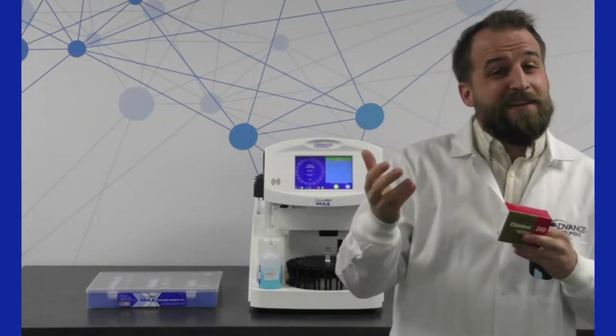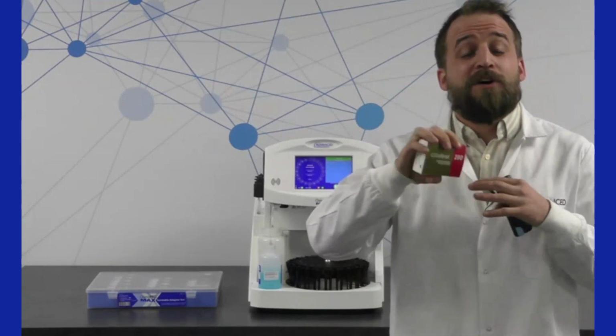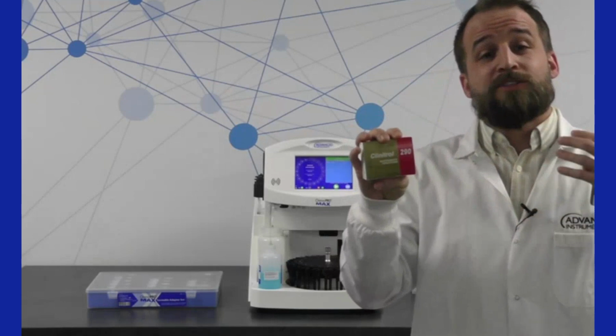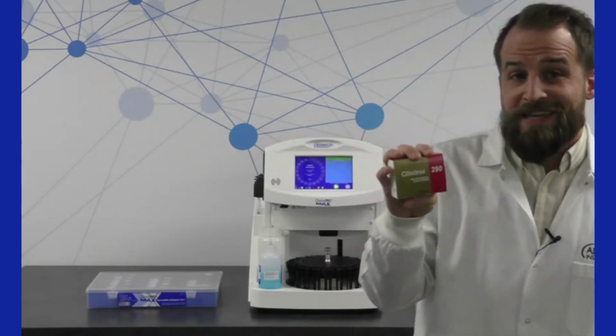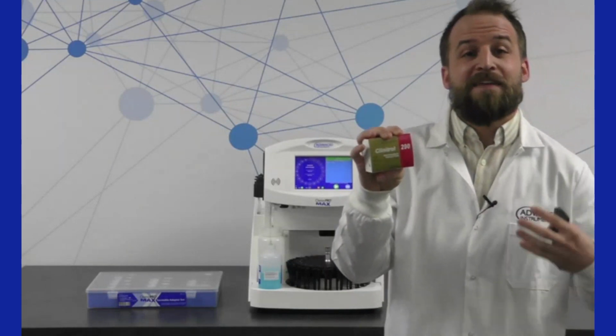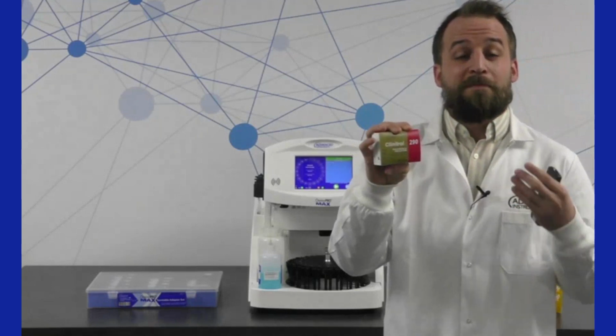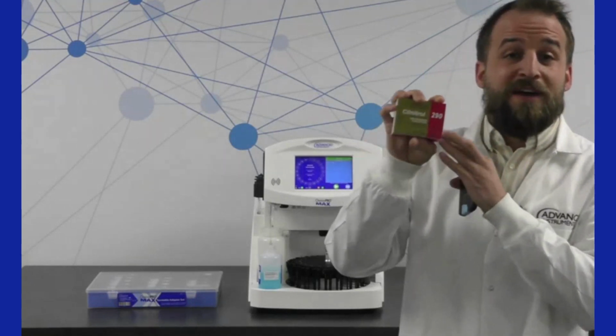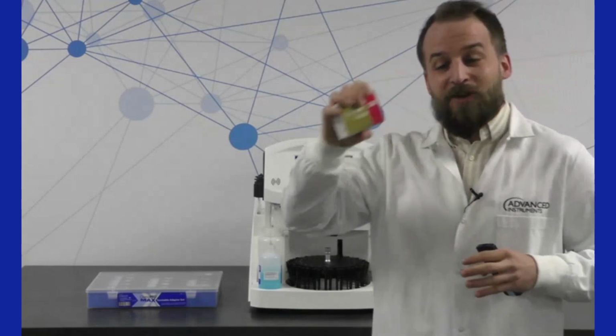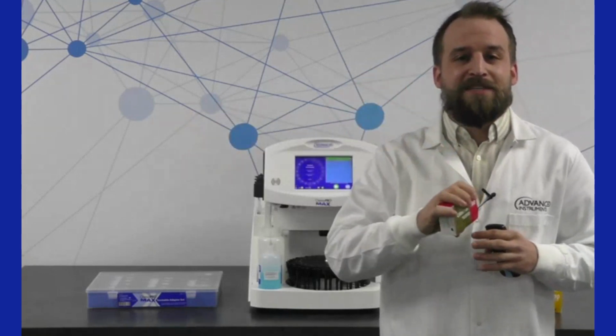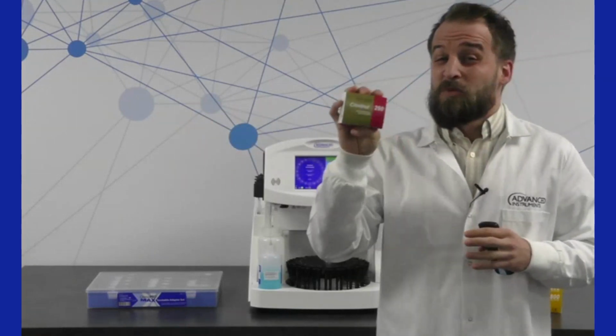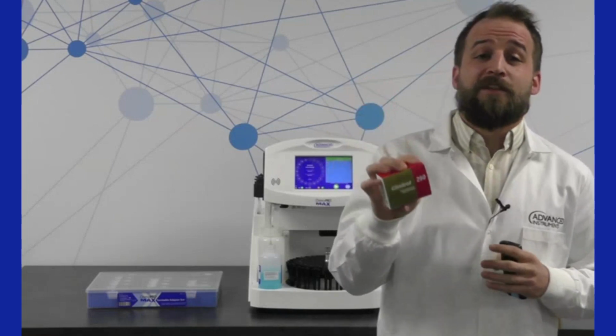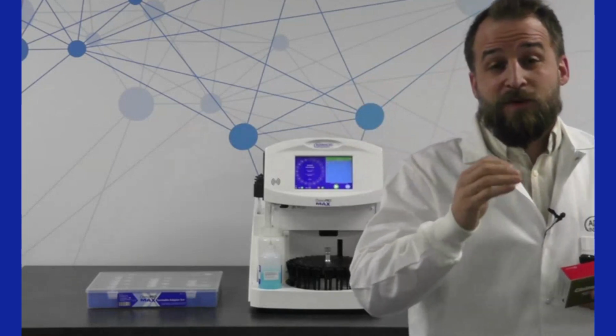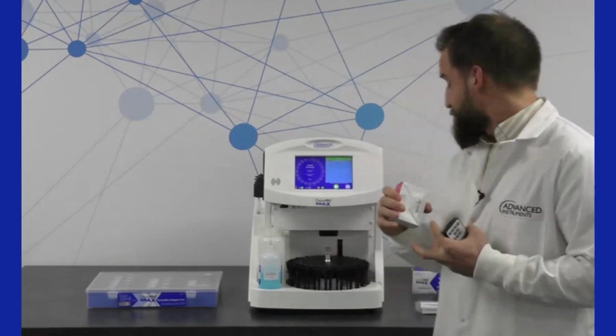If it's outside of that plus or minus 2 milliosmol, but within plus or minus 6, then, kind of likened to a blood gas analyzer, it will automatically perform what's called a single point adjustment. It will prompt the instrument to run another 290 test one more time just to verify that the single point adjustment rebaselined the 290 result appropriately. And then your QC will pass and you can continue testing as normal after that as well. Super rare, but just an added level of assurance to maintain the consistent, reliable performance of your instrument.